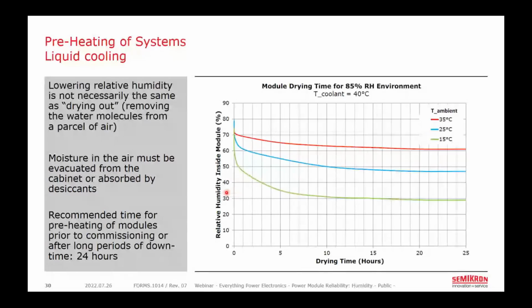However, we know from a few slides ago that this doesn't necessarily mean that the absolute humidity has changed, and there may still be water vapor present within the silicone gel. And so therefore, the coolant should be applied for a longer duration if we really want to drive those water molecules out of the silicone gel prior to starting electrical operation. So based on experience, for example, in the wind industry, we generally recommend running heated coolant for 24 hours if the system is being commissioned for the first time, or if the system has been inoperable for a long period of time.